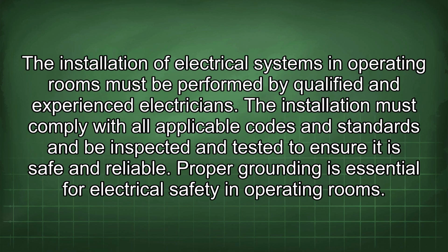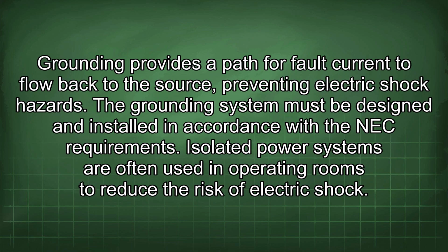The installation of electrical systems in operating rooms must be performed by qualified and experienced electricians. The installation must comply with all applicable codes and standards and be inspected and tested to ensure it is safe and reliable. Proper grounding is essential for electrical safety in operating rooms. Grounding provides a path for fault current to flow back to the source, preventing electric shock hazards. The grounding system must be designed and installed in accordance with the NEC requirements.